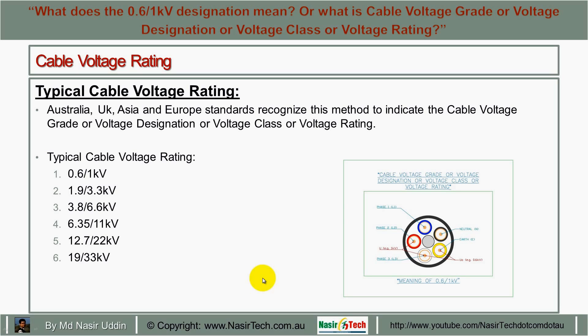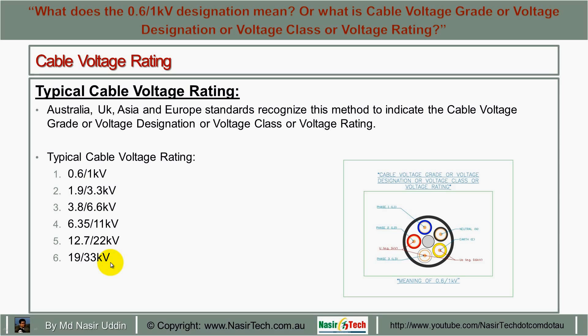Manufacturers provide this information for any kV voltage rating in this format for different types of applications. Typical cable voltage ratings include: 0.6/1 kV, 1.9/3.3 kV, 3.8/6.6 kV, 6.35/11 kV, 12.7/22 kV, and 19/33 kV. For higher voltage installations we can find higher voltage rated cables as well.